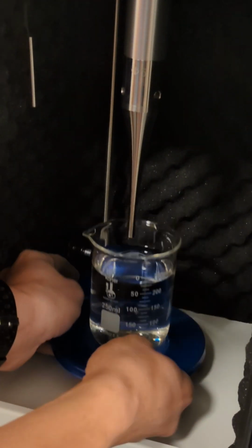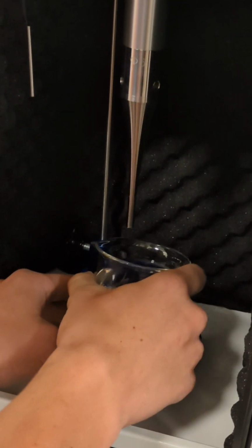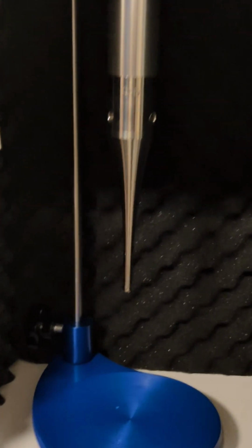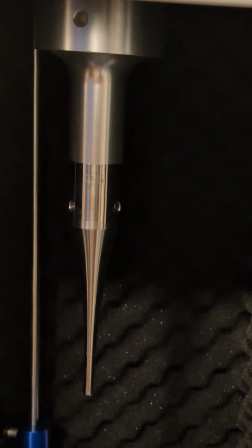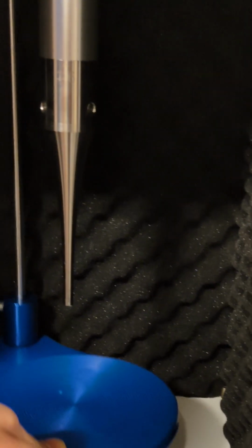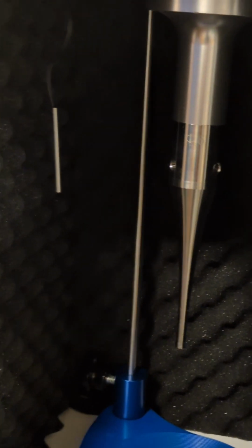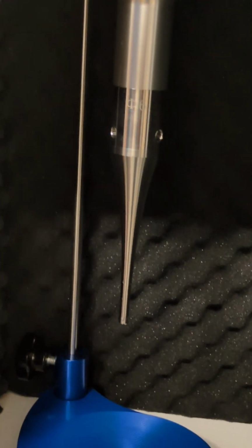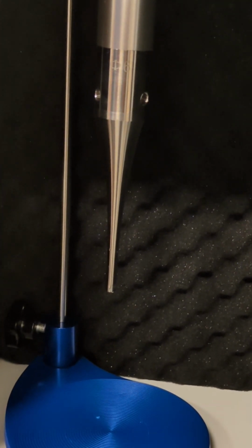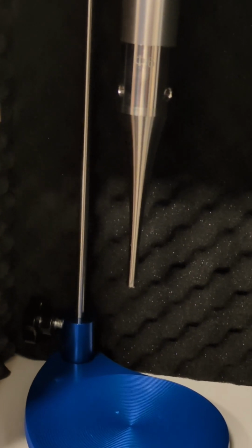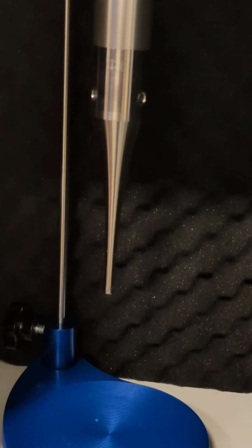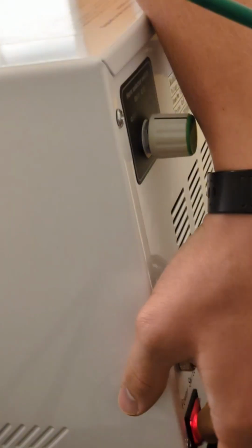So once it's done, we just lower the platform like we raised it and take our sample out, being careful not to ever touch or bump the horn. Once you're done testing, you'll also need to clean the probe. This should be done by running it again in an appropriate solvent or deionized water, and then using something like a Kimwipe, a lint-free cloth, to very delicately dry it off so that no corrosion forms. So then once you're done, just turn it off again, and thank you for watching.